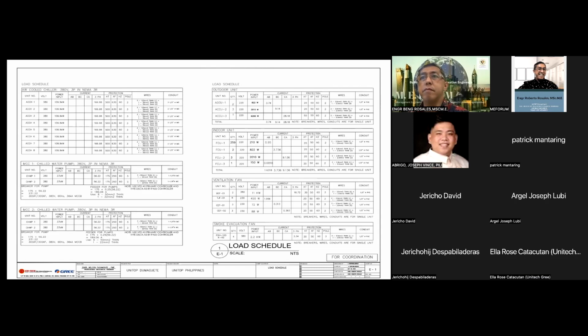Now, rule number one, when you're designing an electrical system, one breaker is equivalent to one motor. You cannot place two or more motors in one single breaker. Why? Because, like I said a while ago, meron tinatawag na starting current at inrush current.